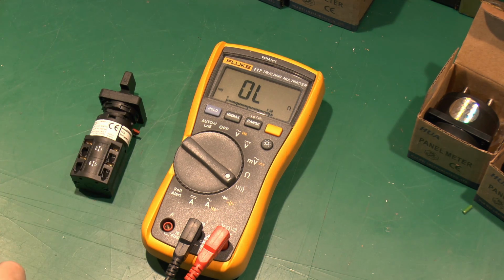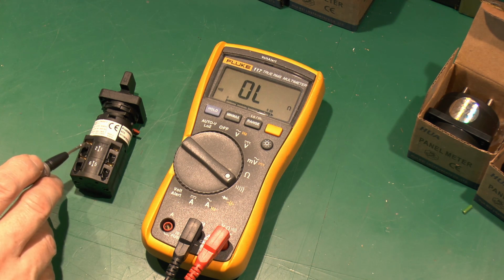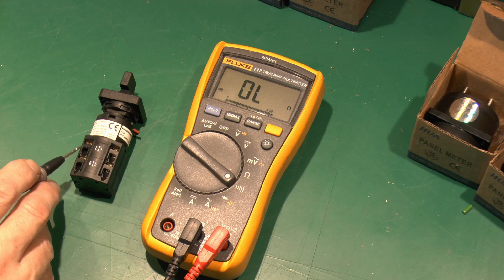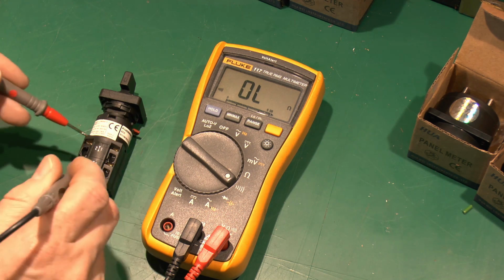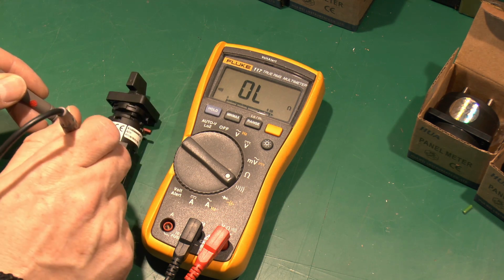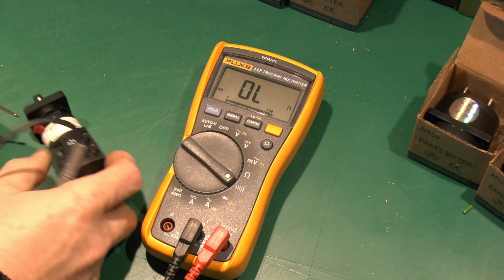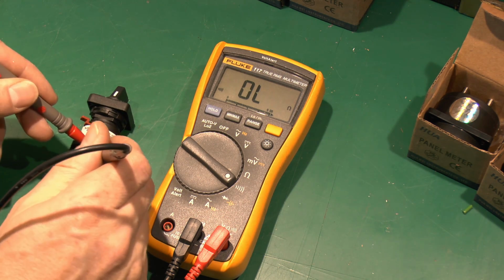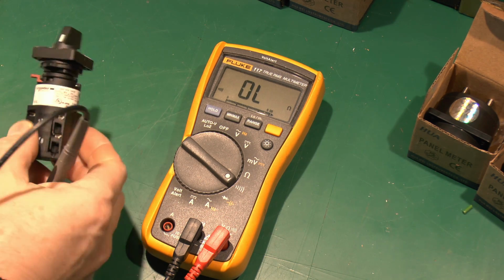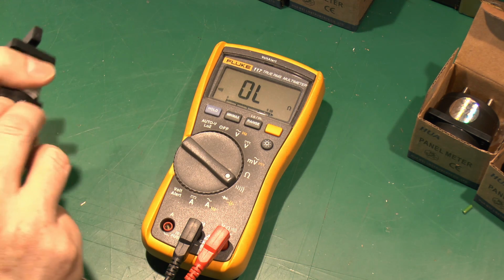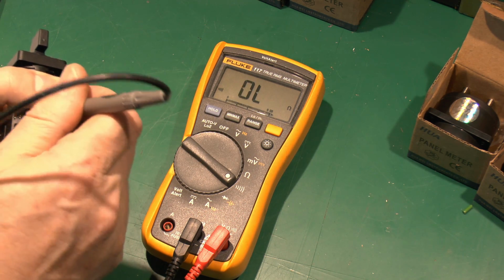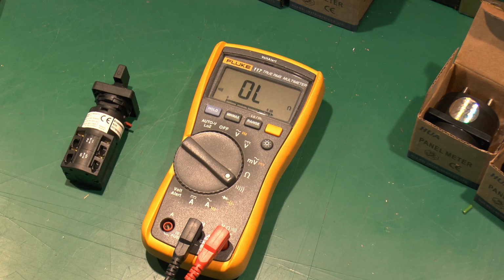Now according to the information provided, the input should be number 2 over here, and that's also commoned up with 2, 4, 6 and 8. So regardless of the position, we should have continuity between 2 and 6. There should also be continuity between 4 and 8, and there should also be continuity between any of those, such as 4 on the back and these on the front, which there is, so that's fine.